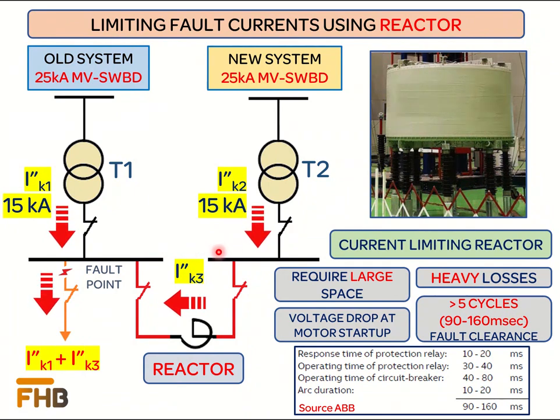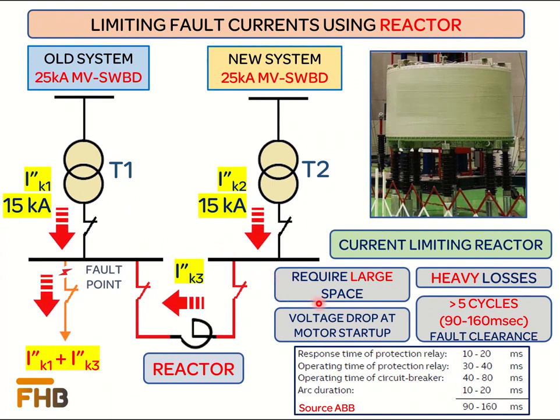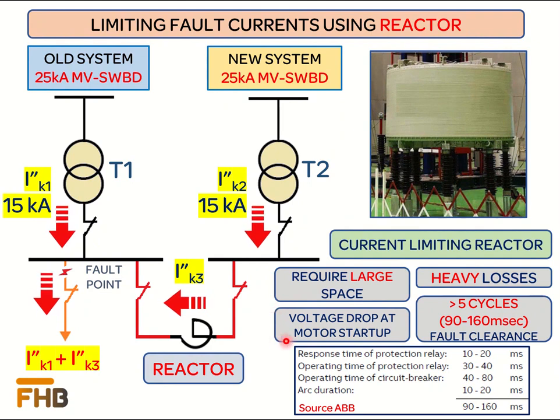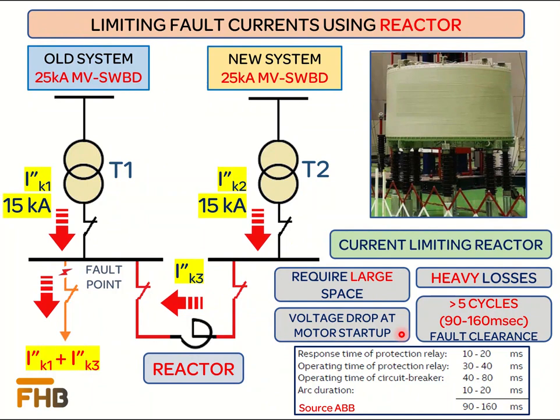However, during normal operation these reactors introduce several problems in the power system. These reactors are large, therefore a separate room is required for installation. Since current continuously flows through the reactor, additional power losses are introduced in the system. If the reactors are installed directly in line with large motors, the voltage drop at the time of motor starting will increase and can cause problems during motor startup. It is therefore suggested not to install reactors in the path of large inductive loads.